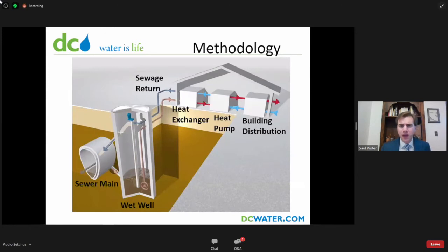So just to make sure everybody understands what we're talking about, the system is directly analogous to a geothermal system where you exchange your thermal energy with the ground. Here, we're taking sewage out of the sewer main at the left-hand side of this image. And in this particular application, it drops it into a wet well, though that's not always necessary. It's then screened to take out the large debris or things that would otherwise interfere with a heat exchanger, pumped out of the wet well, goes through a heat exchanger, and that's the last that the sewage is actually handled.